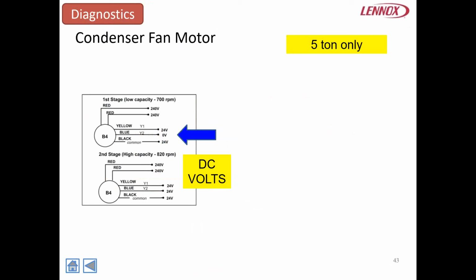On the XP16 we talked about yesterday, only our 5-ton currently uses the DC voltage and line voltage. It's very much like an X13 motor, requiring both high and low voltage to operate. Again, we are talking about DC voltage on the low end.